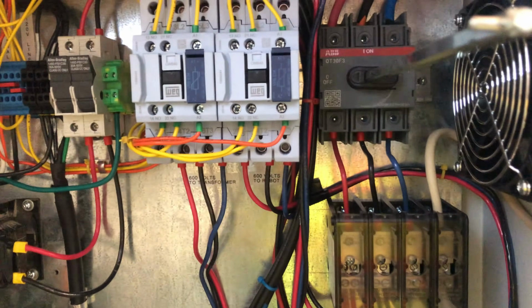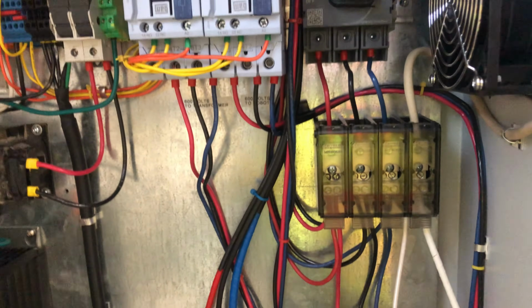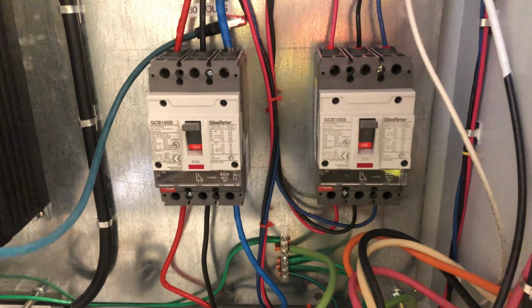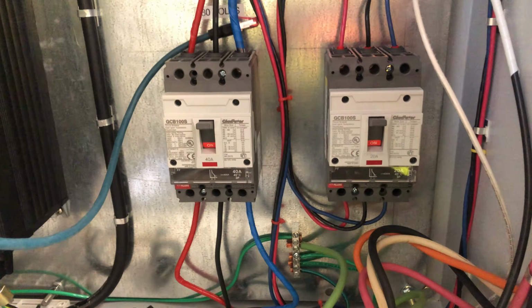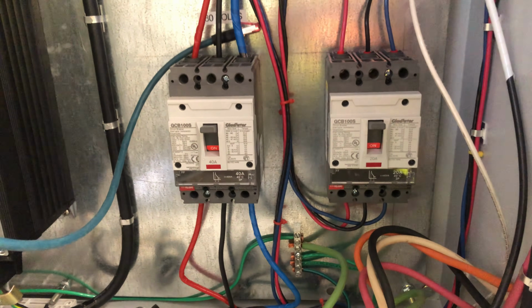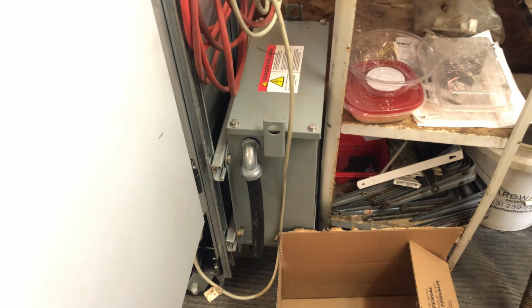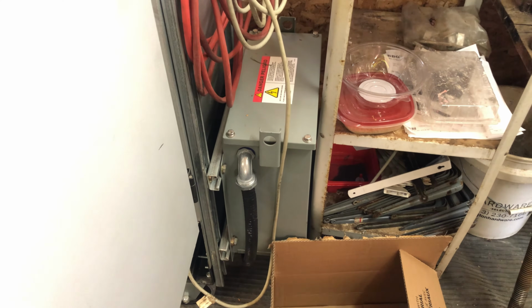So it comes into here, this simple on-off switch, and then down to this terminal block. From there it splits into two circuits. One is a 20 amp breaker that protects the control cabinet for the robot, and then power goes straight from this terminal block for the other circuit over to another transformer I've got here. This is a 30 kVA 600 volt to 480 volt 3-phase transformer.